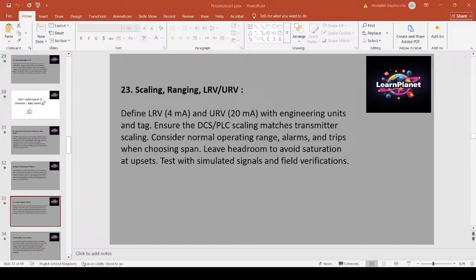Correct scaling maps the sensor electrical range to engineering units in the PLC, DCS, and HMI. Mismatches cause wrong displays and potential trips. Define LRV and URV, 4 to 20 mA, on field devices and in the controller. Record units and tolerances. Select spans so normal operation uses the central portion of the range for resolution, with headroom for excursions. Simulate and test with a handheld calibrator to confirm end-to-end scaling. Example: a pressure transmitter is ranged 0 to 100 bar, but the controller was set 0 to 10 bar. Fix the scaling to avoid false high alarms and trips.